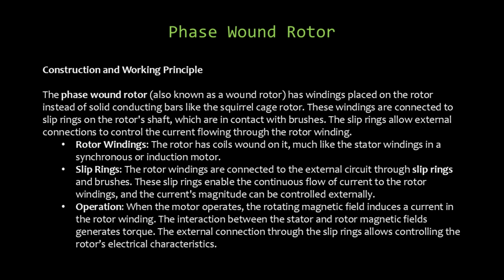Now, let's explore the phase wound rotor, also known as a wound rotor. Unlike the squirrel cage design, this rotor features windings placed directly on the rotor. These windings connect to slip rings on the rotor's shaft, which interface with brushes. This unique configuration allows external connections to control the current flowing through the rotor winding, providing more flexibility in motor operation. The phase wound rotor's key feature is its specialized winding system.